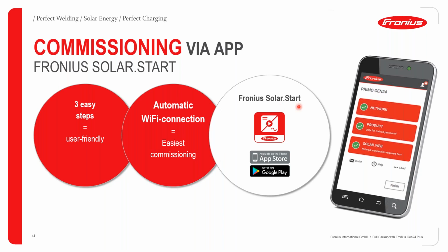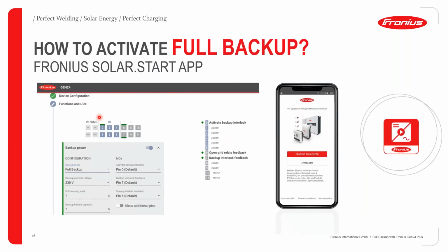Once this is done via Fronius Solar Start, you can now have access to the device configuration, and then you can effectively activate the full backup mode, as can be seen in this screenshot. Once you're done with the device configuration, you can proceed to activate the full backup power using this pin here. Once you click on it, you select your full backup mode, because here you have the option of PV point mode and then full backup mode. Since we're activating full backup mode, you now have to select full backup mode, select your nominal voltage, and then continue. And if you have to do any energy management, you can of course use any of these available pins to activate your energy management pins.